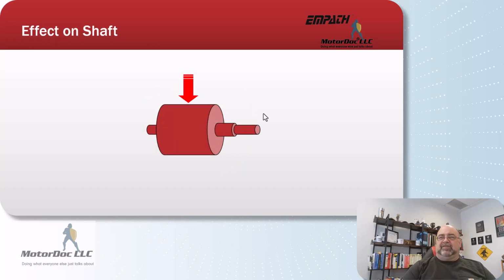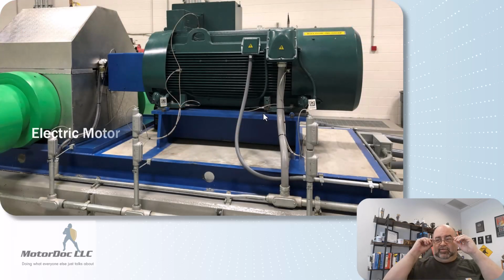Other effects on the shaft include unbalance, that would be radial, torsional, which is torsional related stuff on the air gap, unbalance and misalignment, overtension belt, stuff like that, that's seen there. And smeared laminations will cause the rotor to bow and cause things like dynamic eccentricity. So we're going to circle back to this machine. Actually, we're going to do this machine next. I've got a case study.